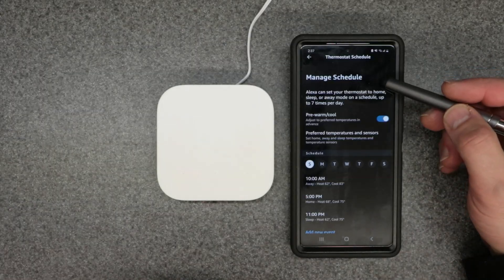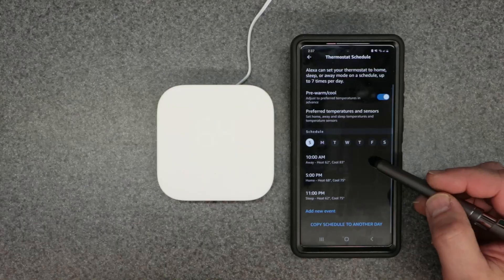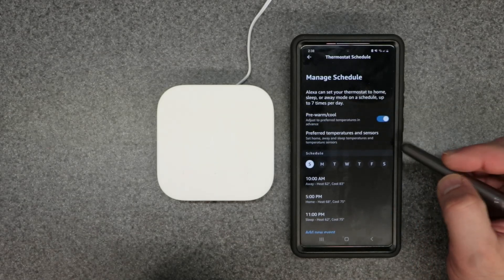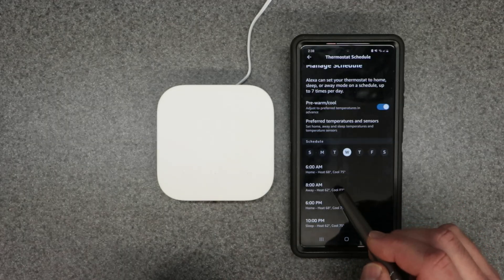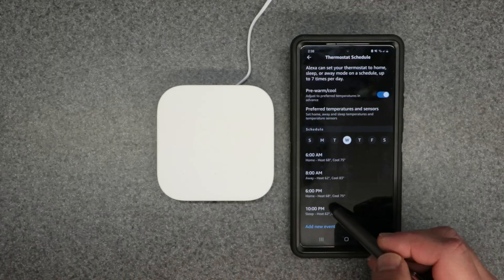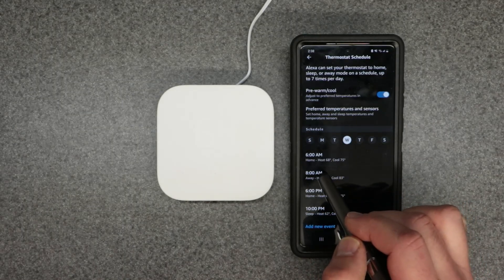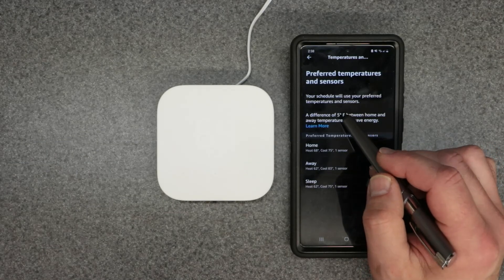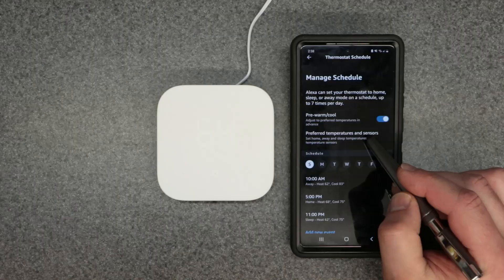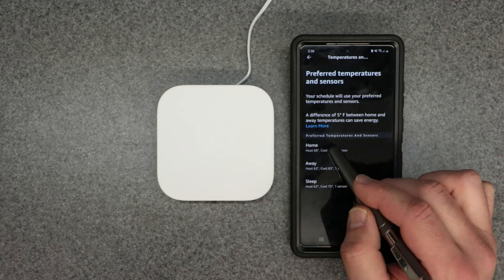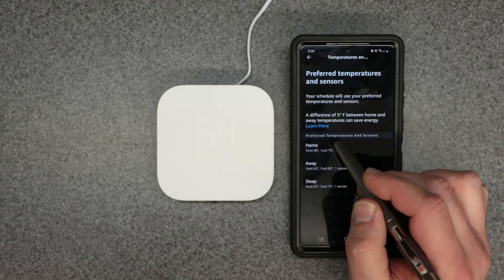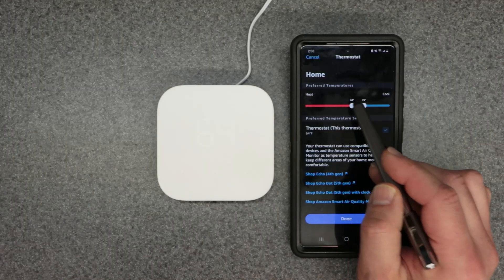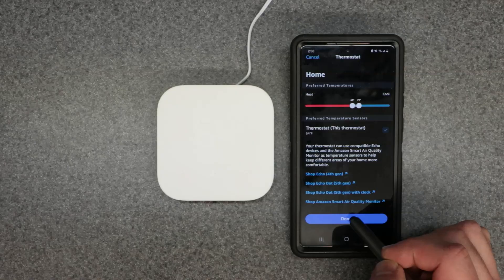On the Manage Schedule screen you adjust thermostat temperatures and time periods. You can program this for all seven days, selecting different events for each day. You set different time frames and set points. Under Preferred Temperature and Sensors, click a period like Home to set your temperature. For auto changeover, you'd set cooling to around 72 and heating to 68, then hit Done.